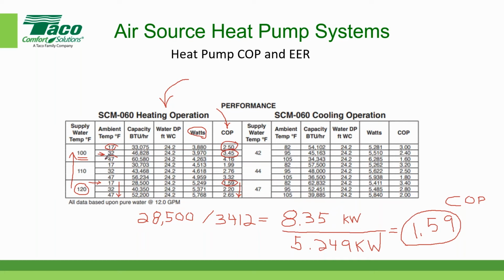You still have to provide some heat. Let's say your outdoor air temperature is 47 degrees. Look at this. The COP jumps way up to 4.16. So that's why heat pumps are so attractive, especially when we're talking about electrification, because the majority of the hours they operate in more reasonable ambient temperatures, and they can discharge relatively low temperatures if the distribution system has been properly designed and selected to operate on relatively low temperatures.